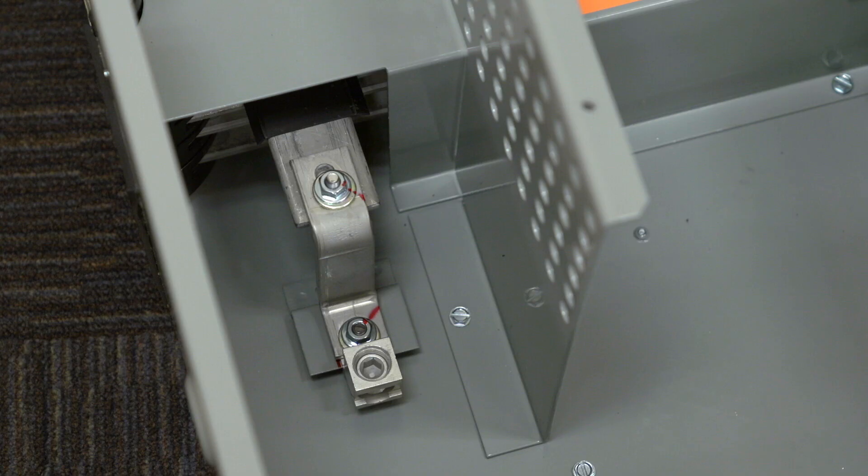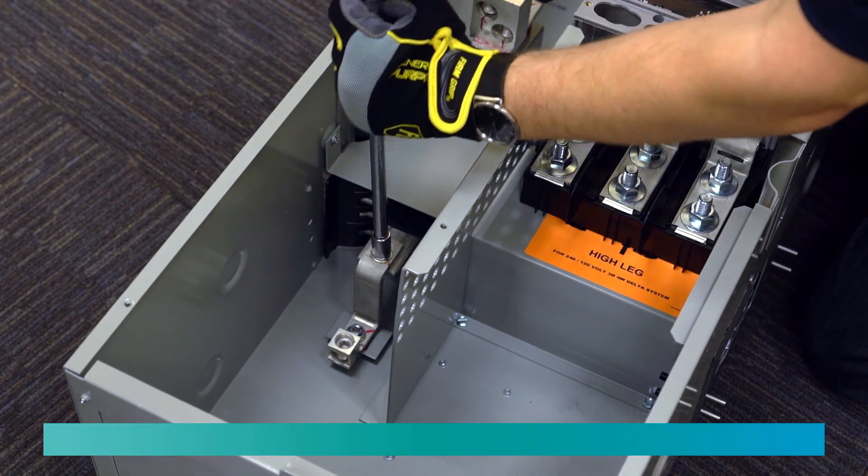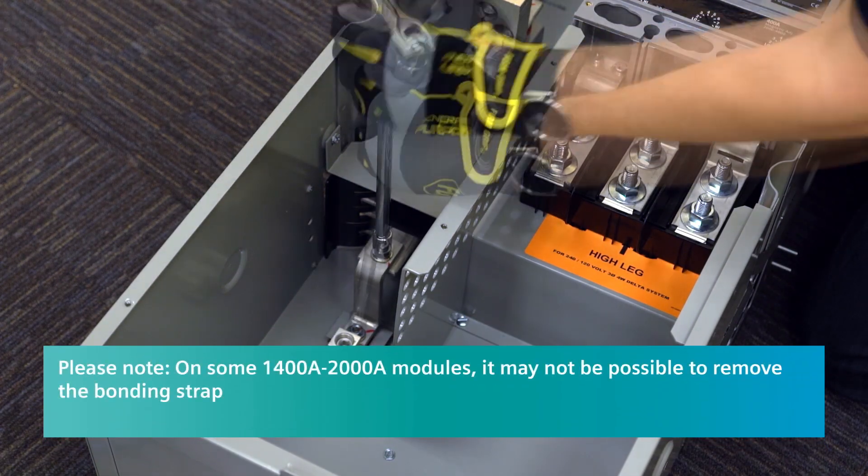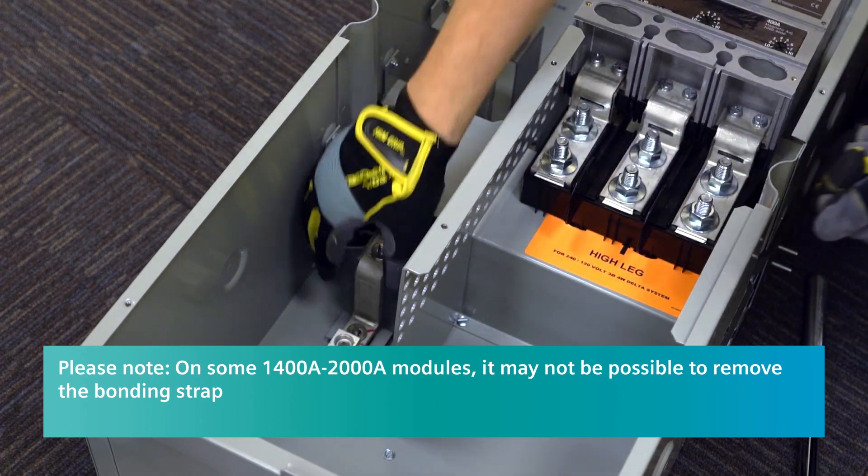All PowerMod service entrance main devices come with a neutral and ground bonded. If the module needs to be used in a non-service entrance application, the bonding strap between the neutral and ground must be removed.